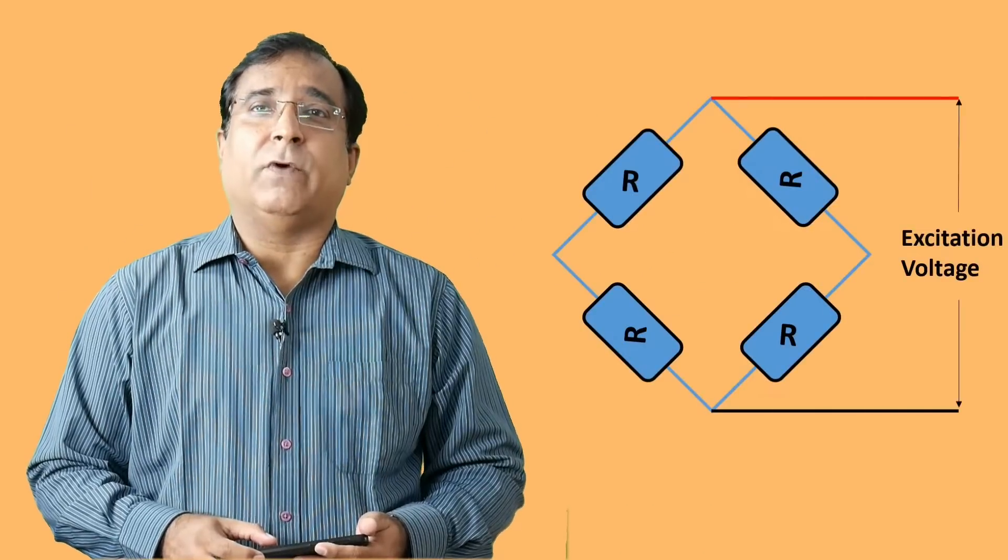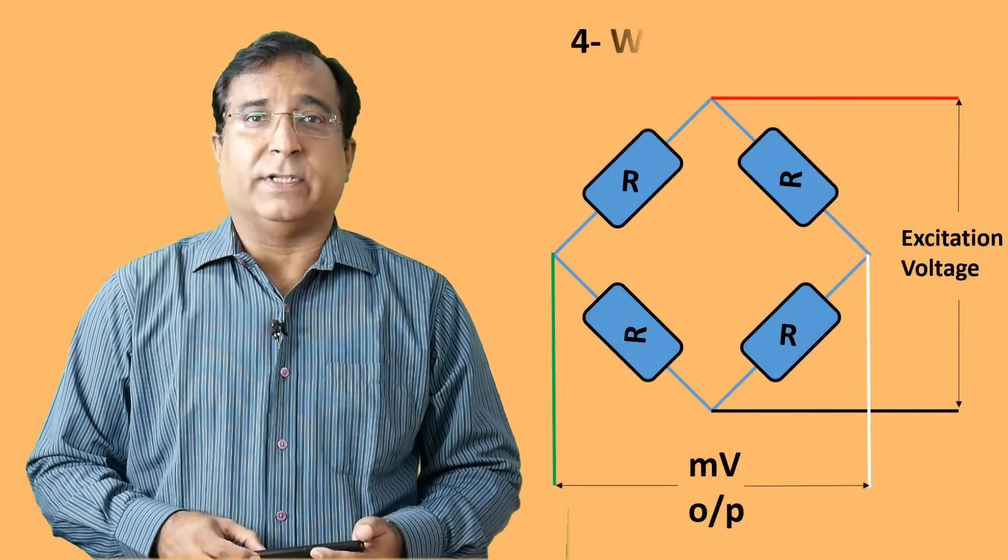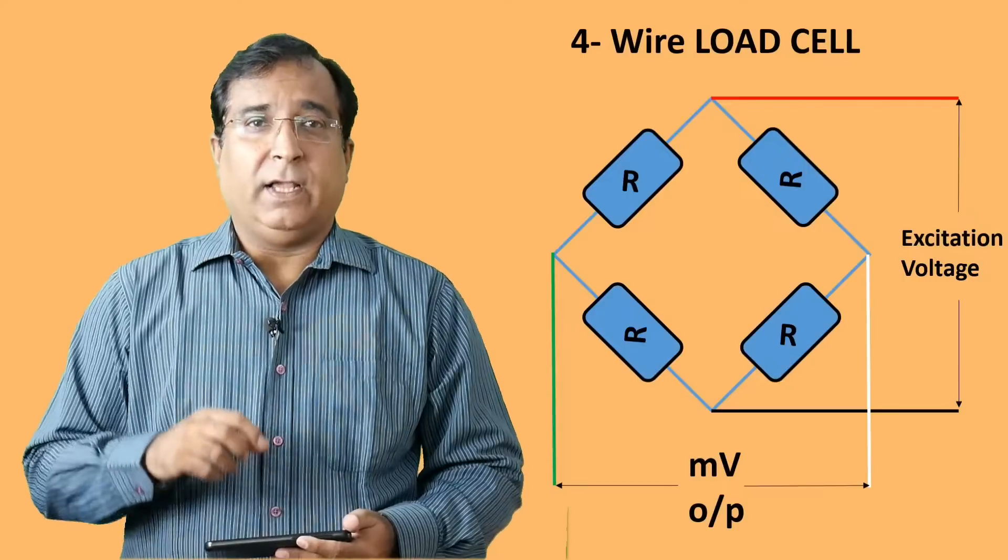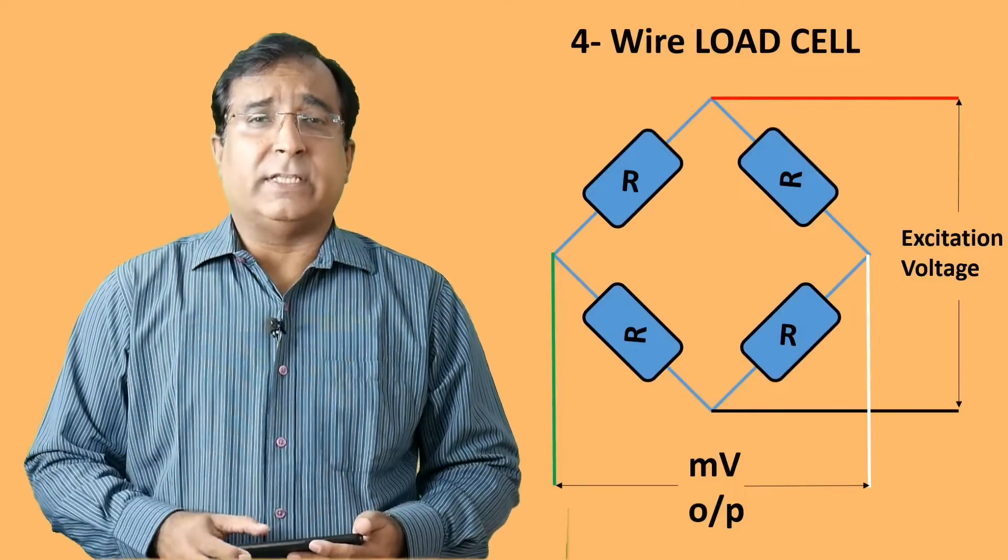There is a bridge with 4 wires comes out of a load cell and excitation voltage is given on the 2 wires at opposite end of bridge and signal output is taken from the other 2 ends. Now the load cell is described by 4 wire or 6 wire also.